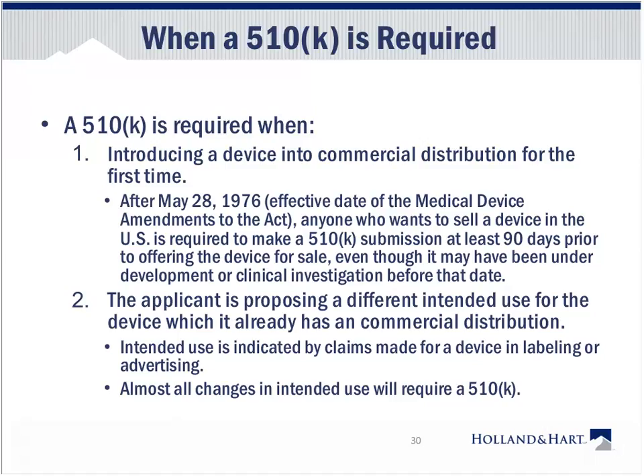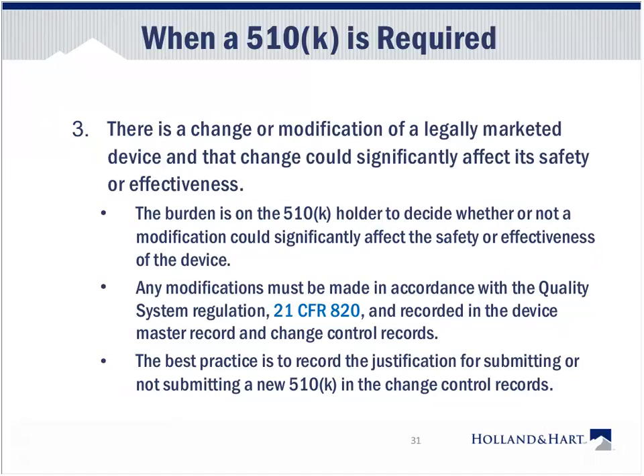Number two, a 510K is required when the applicant is proposing a different intended use for a device which already has a commercial distribution. So if you've figured out a new use for an existing product, it will still require a new 510K submission to look at the safety and effectiveness of that device for the new intended use. Number three, there's a change or modification of a legally marketed device, and that change could significantly affect its safety or effectiveness. Again, we come back to this nebulous concept that there is no form and no specific requirements, and this adds to it. The burden is on the 510K holder to decide whether or not a modification could significantly affect the safety and effectiveness of a device.